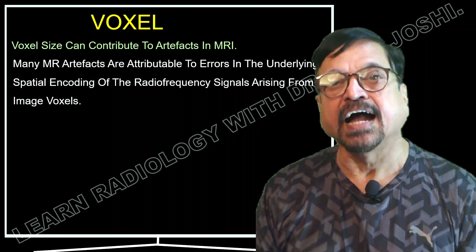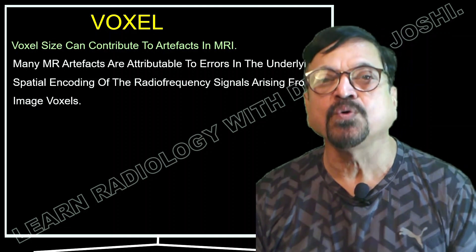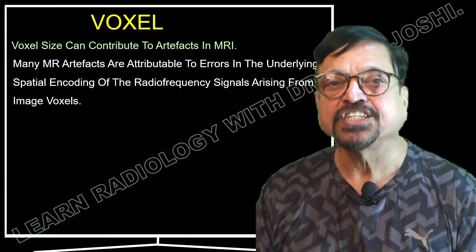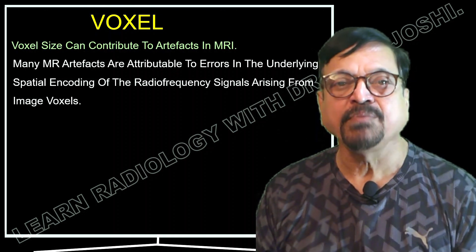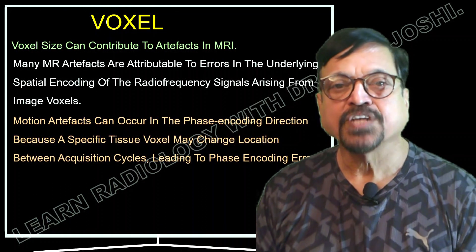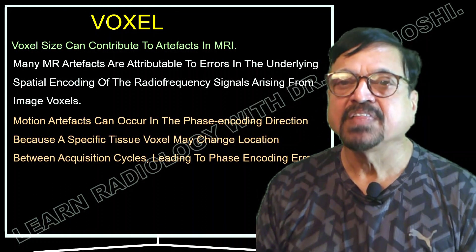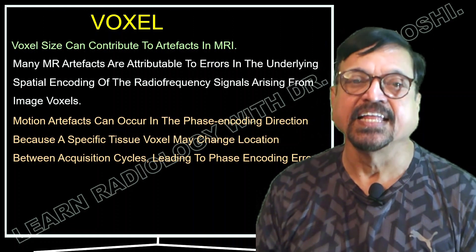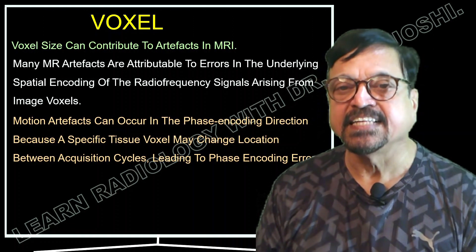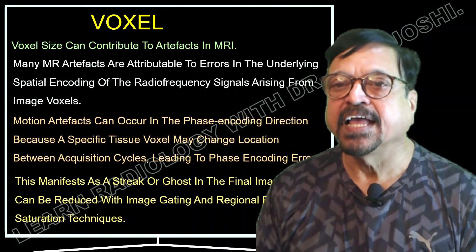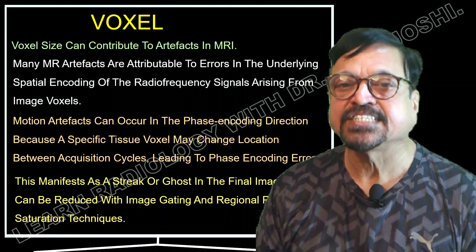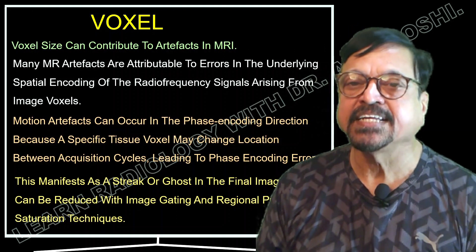Voxel size can also contribute to artifacts in MRI. Many MR artifacts are attributed to errors in spatial encoding of the radio frequency signals arising from the image voxel. Motion artifacts can occur in the phase encoding direction because a specific tissue voxel may change location between acquisition cycles, leading to phase encoding errors. This manifests as streaks or ghost artifacts in the final image, and can be reduced when image gating and regional pre-saturation techniques are used.